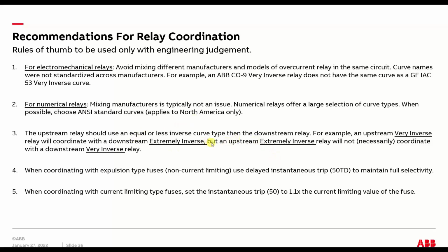Yeah, this is kind of important. Usually you try to keep the type of curve, whether it's extremely inverse or very inverse, the same on all your devices. But you can do otherwise as long as your upstream stuff is less inverse. For example, a very inverse relay upstream will coordinate just fine with an extremely inverse relay downstream, but the opposite's not true. An extremely inverse relay that's downstream will conflict with a very inverse relay that's upstream. So the rule of thumb is to try to keep them all the same curve type when applicable and possible, and if not, always have your less inverse curve upstream.